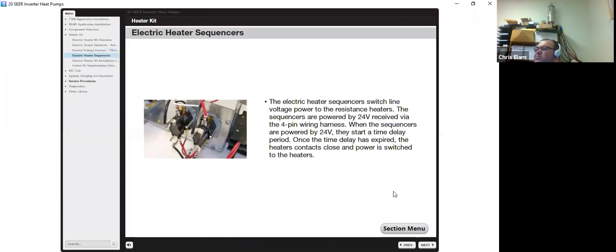You also have electrical sequencers. The electrical sequencers switch line voltage power to the resistance heaters. The sequencers are powered by 24 volts via the 4-pin wiring harness. When the sequencers are powered by 24 volts, they start a time delay period before they come on. That way not all your elements are kicking on at one time. Once that delay is expired, the heater's contacts close and the power is switched on to the heaters. In the reverse cycle, once you lose your call for heat, the timing will kick in again and start counting down. So each element will be shut down one at a time and not all at once.